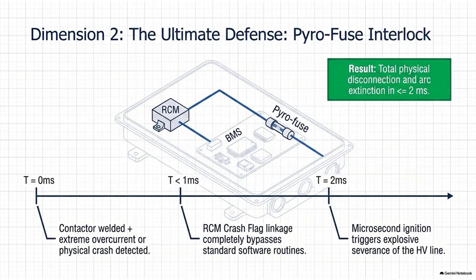Exactly. The RCM sends a massive hardwired voltage pulse directly to the squib inside the pyro-fuse. Inside that sealed fuse housing is a miniature, precisely calibrated chemical explosive charge. Wow. The charge detonates instantly. The kinetic energy of the explosion physically tears the thick, high-voltage copper conductor violently apart. Furthermore, the mechanism uses the explosive force to drive a solid wedge of non-conductive, arc-quenching material directly into the newly created gap to physically smother and extinguish any potential plasma arc.